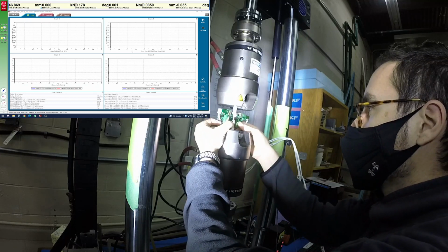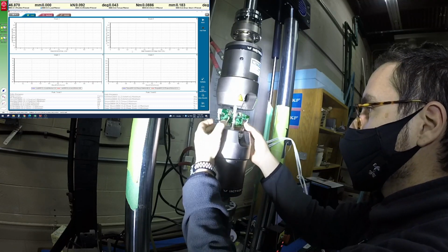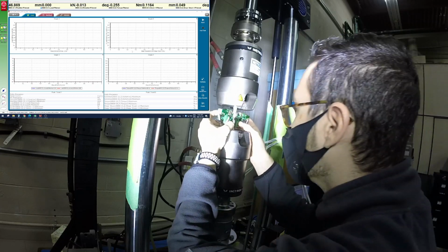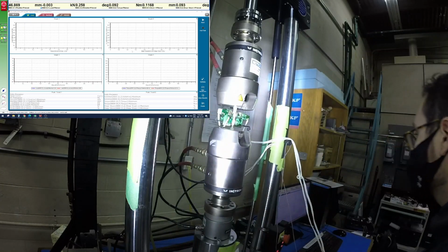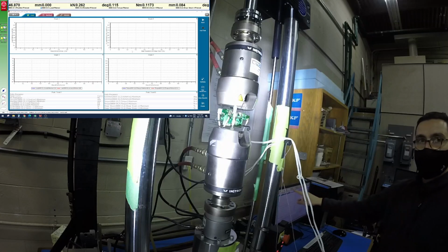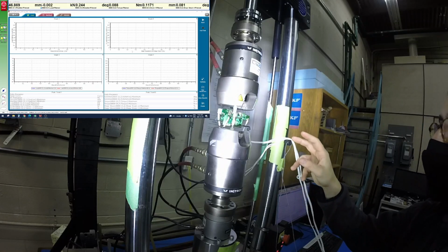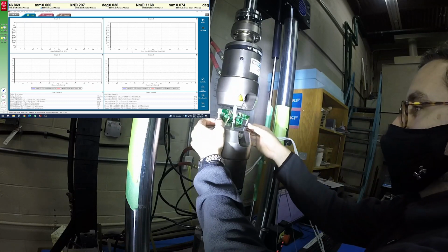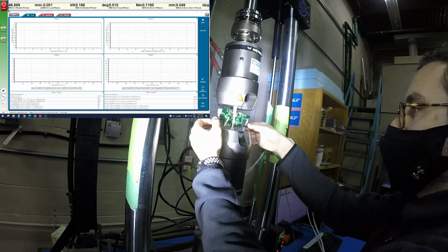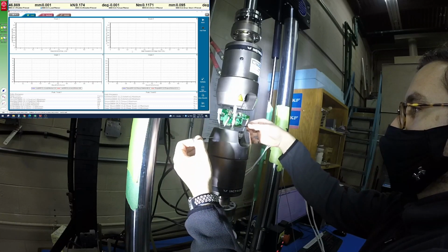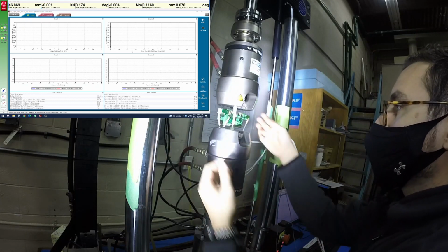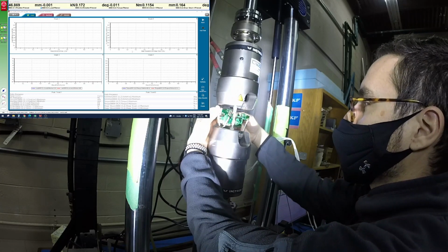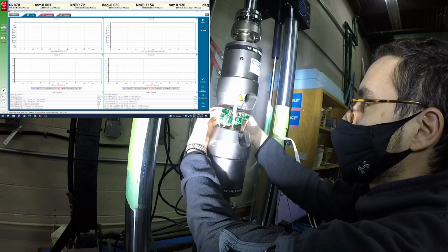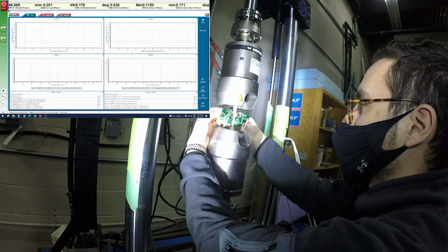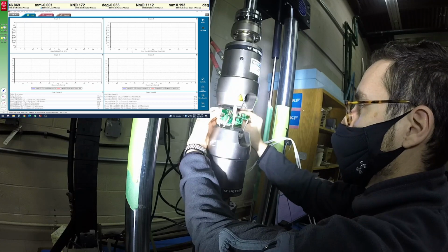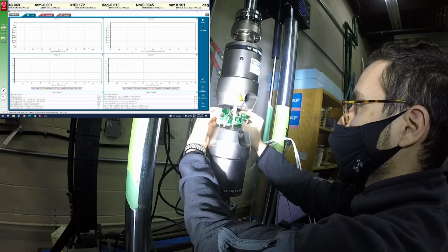So you can see that we can actually pick it up and move it around if we need to adjust anything, but we want it to be biting into the surface. And then you can see, because this sample is being controlled under load and torque control right now, once we pull these pins out, we will release the extensometer to move freely, and effectively this will allow it to follow the movements of whatever the sample is doing, because those pins are now biting into the surface. To make it a little bit easier to remove these, I like to twist the pins to stop any excessive bending or load being applied.